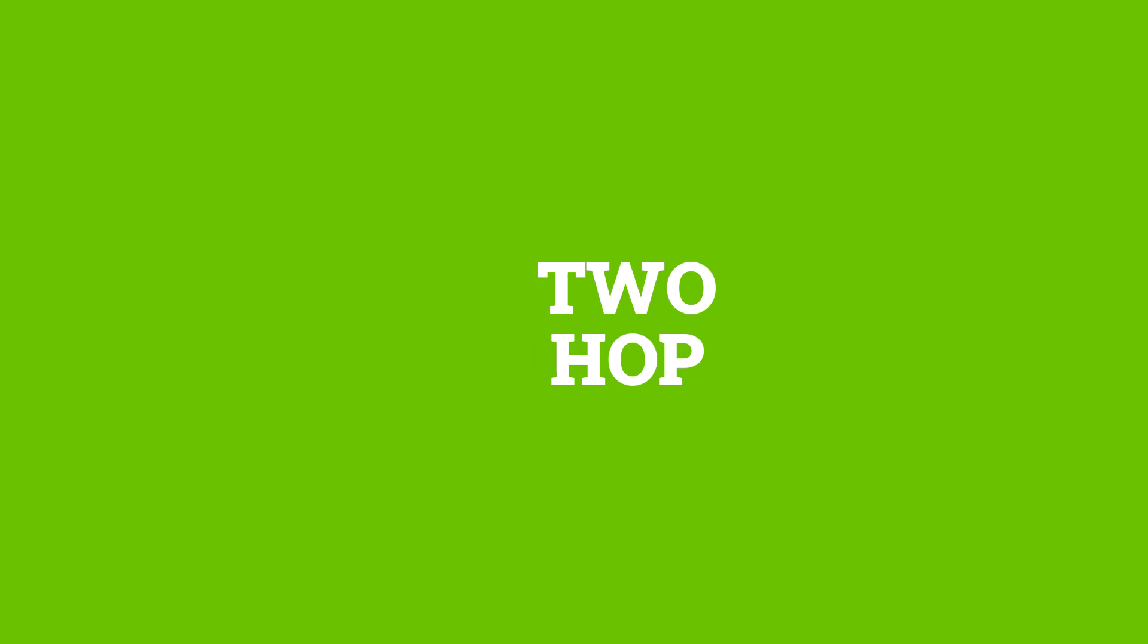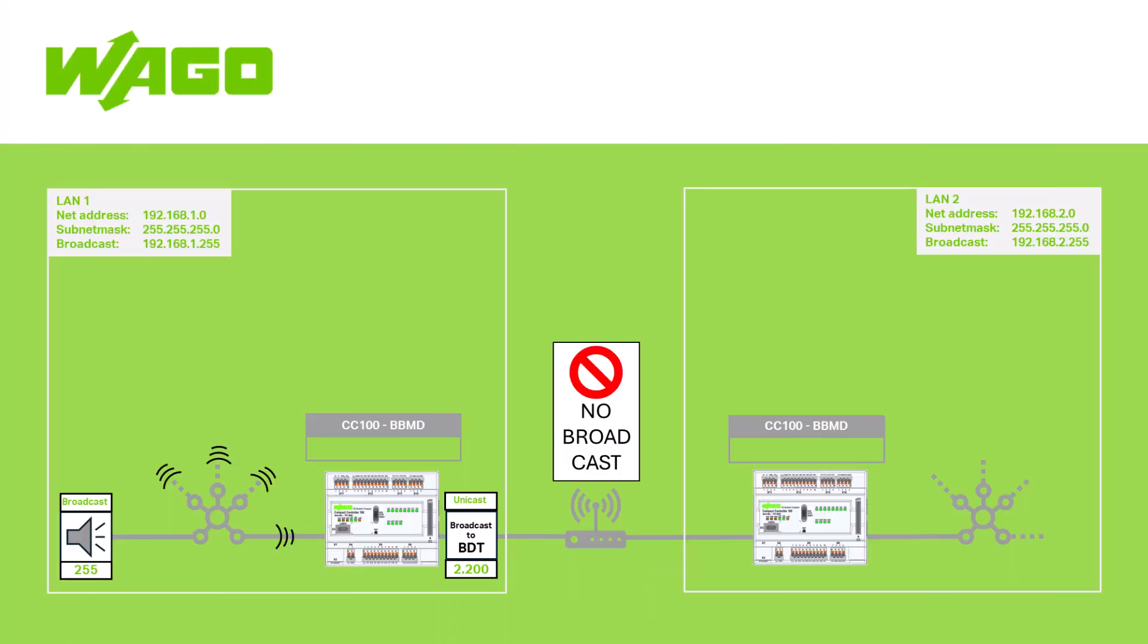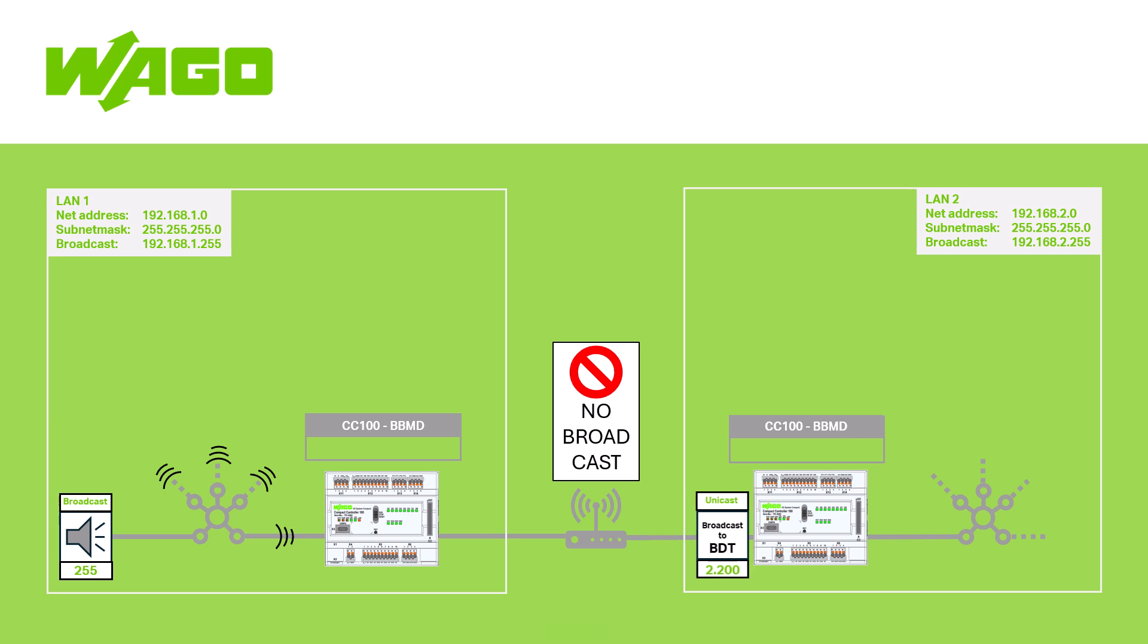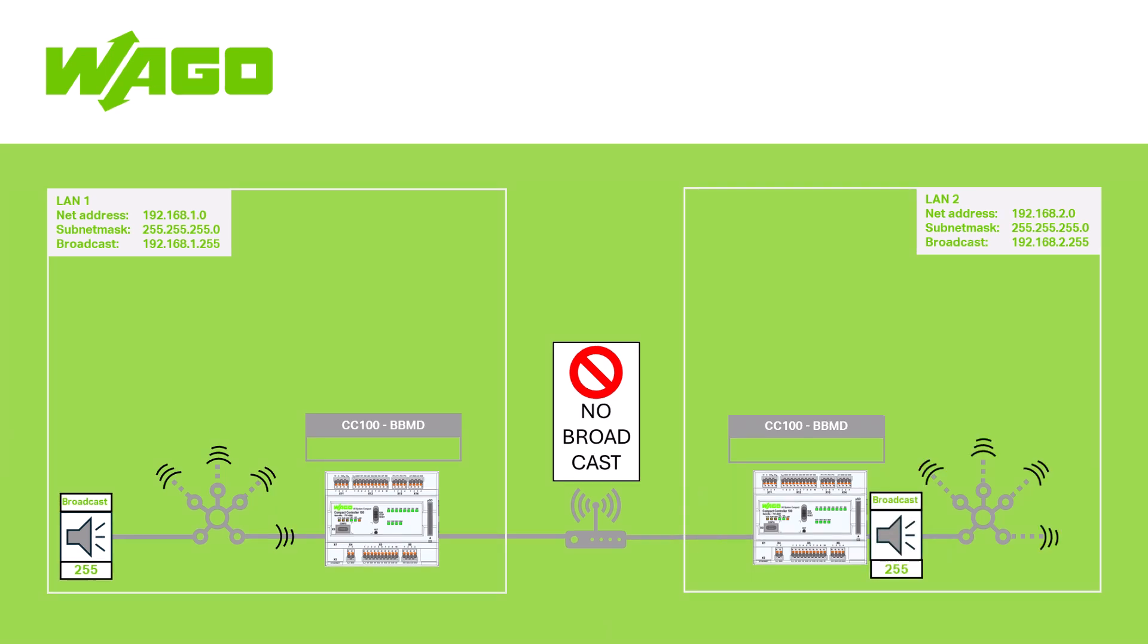The now common method of doing this is called the 2HOP method. In this method, one BBMD forwards broadcast messages to another BBMD on the remote IP subnet. This BBMD then distributes the messages on its local network as IP broadcast messages from its IP subnet.